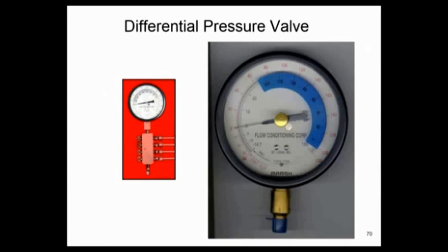This particular gauge, by the way, for a specific gravity of one, has feet of head built into it for you, which makes it easier sometimes to make people understand and read versus psi. Because all your pump curves are going to be in feet of head, and most of your gauges are going to be in psi. So if you can assume that specific gravity is one, like for water, you can buy a gauge that's got feet of head already built into it and make it easier for everybody to find your 63 feet.